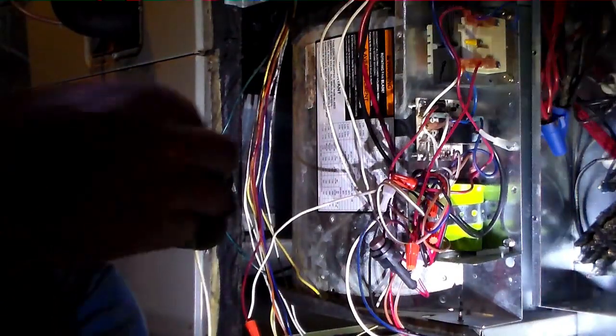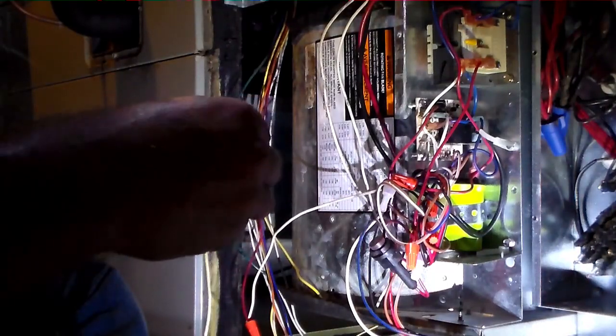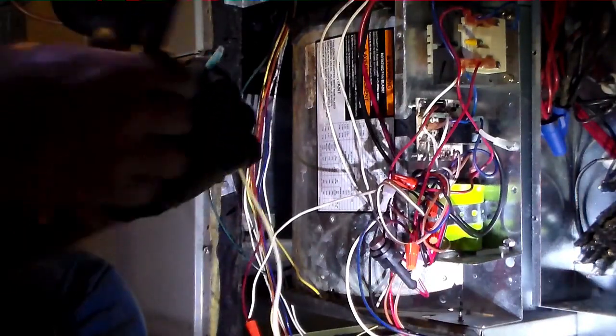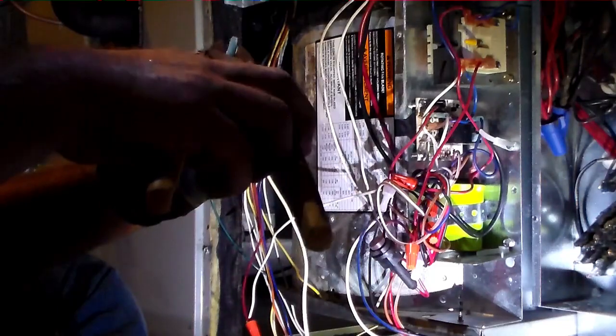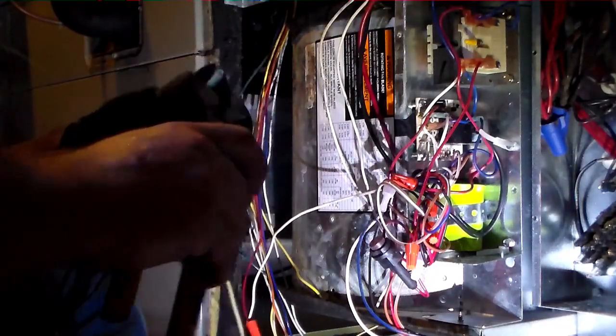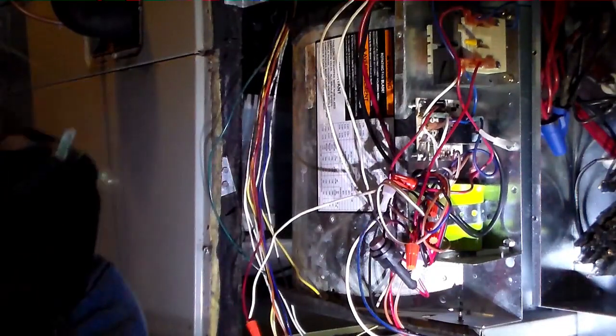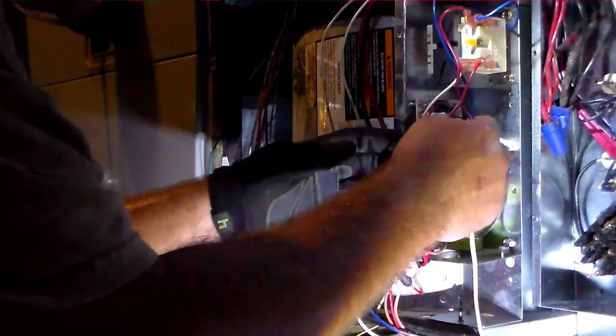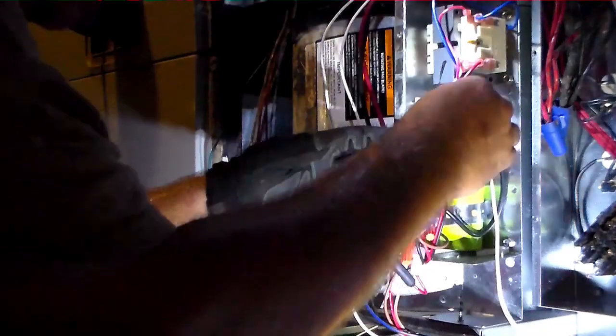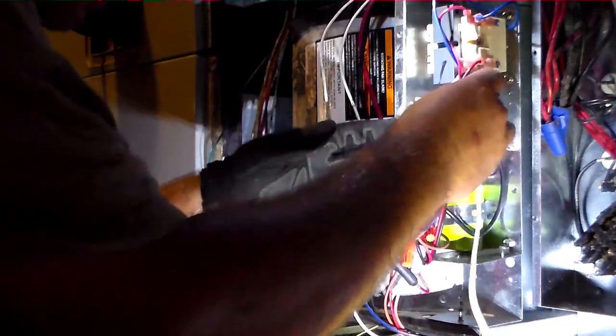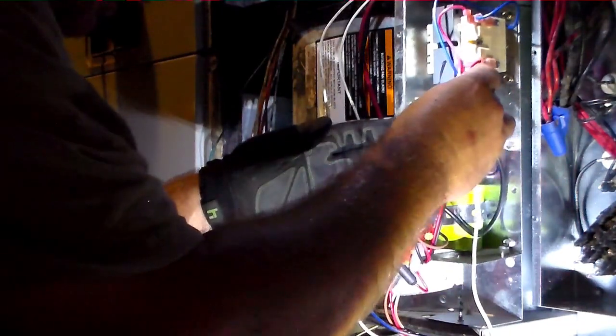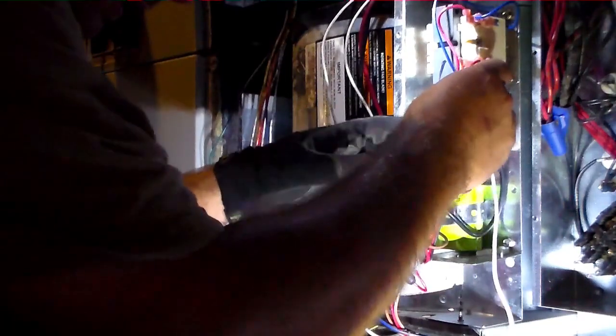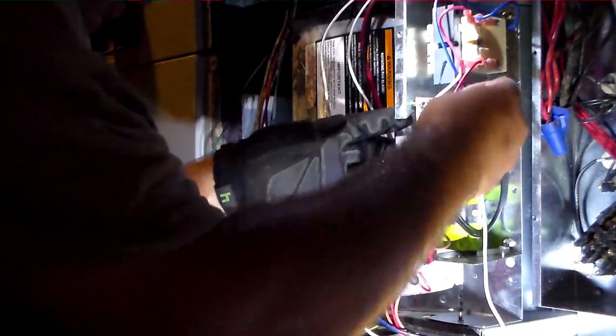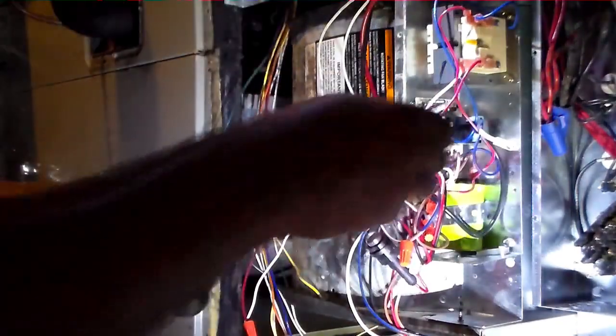And we're going to run it over to the common on the blower control board, which will be right here. We see our blue wire coming in from the transformer. Sandwiched in there we have a kind of piggyback connection on it right now. I'm going into that connection if I can, and I'm going to run it out.